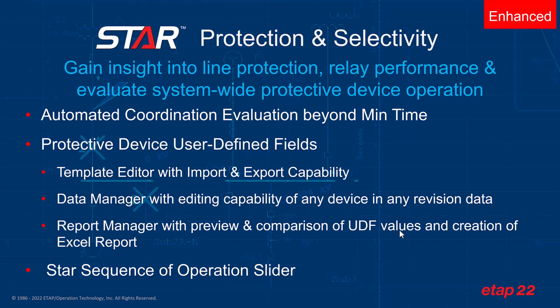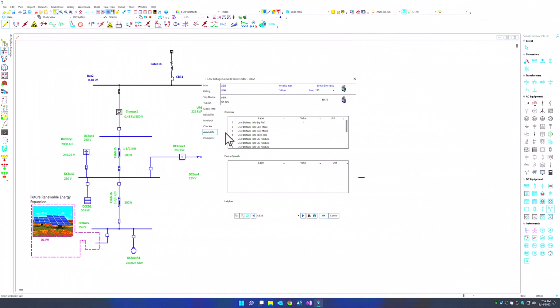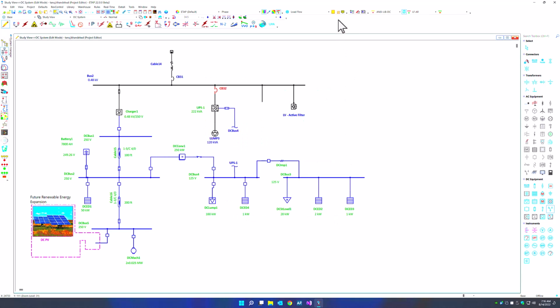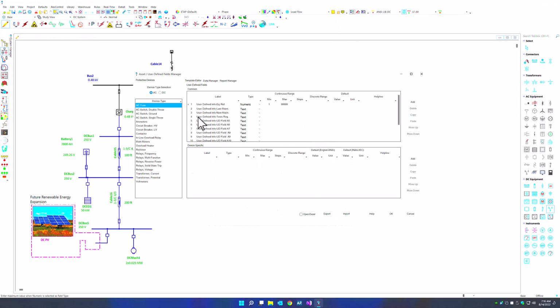Let's take a look at user-defined fields a little bit more in detail in ETAP 22. Each component, such as the protected device, has an asset or user-defined field. All your existing user-defined fields within ETAP have been converted into this easy to use and find table. It includes common user-defined fields as well as device-specific fields. And these common and device-specific fields are driven through a template. So let's open up our template very quickly and observe what happens with one of these devices.